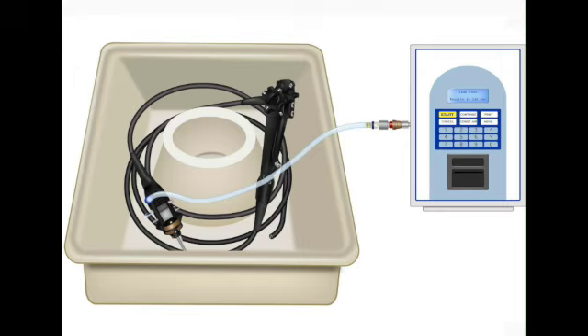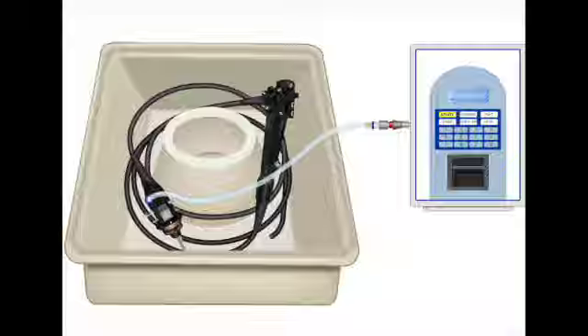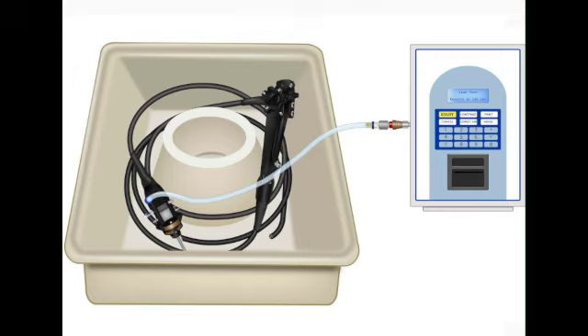The really bad news is outcome number two. There is no visible inflation, no distension at the tip at all. But you know there's a leak somewhere because it failed the test twice. Then what happens? Then you absolutely must not submerge that scope. Do not let it touch a basin of water. Why not? Because no distension means the air is escaping fast, probably from a major breach directly into the core of the scope. If you submerge it, water will flood the internal optics, the electronics. Catastrophic damage. Total catastrophic damage. It's often non-repairable after that, or the bill is just astronomical.